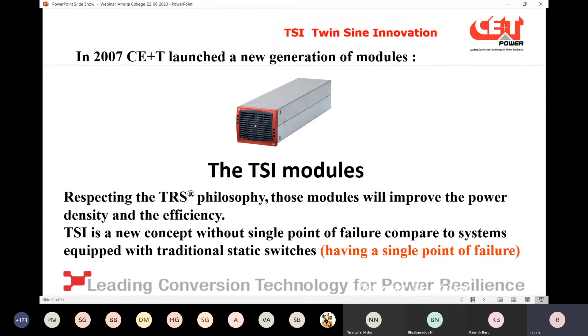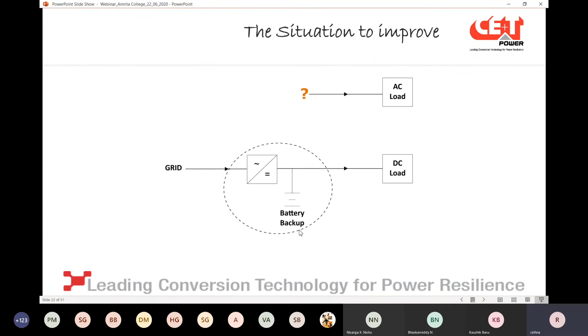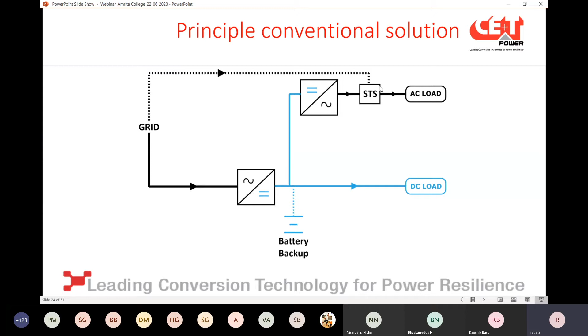Our main goal is to secure the loads, both DC and AC. In telecom, you have the grid feeding rectifiers that convert AC to DC, charge the batteries, and supply the DC load. For the AC load, the conventional solution uses an inverter that converts DC to AC, with a static switch available to then feed the AC load. So what is the disadvantage of this?